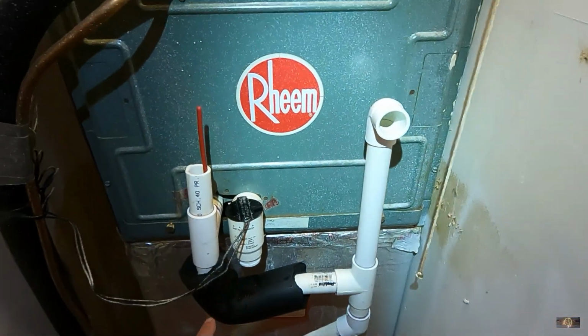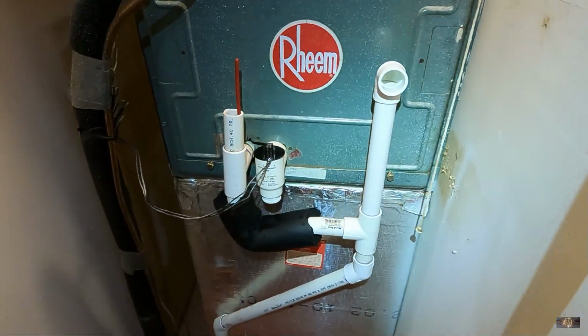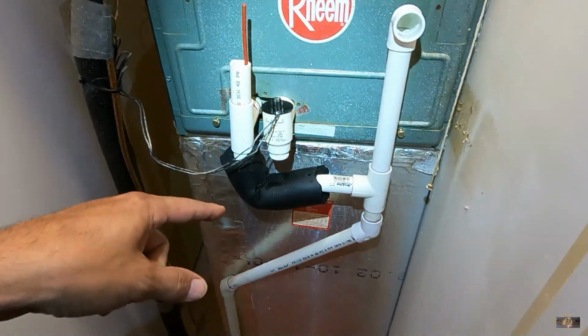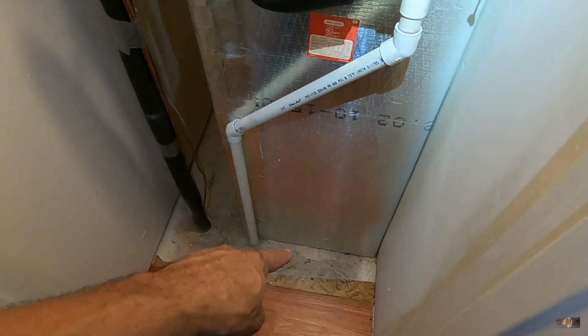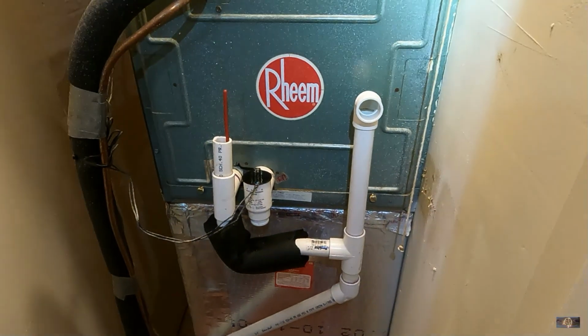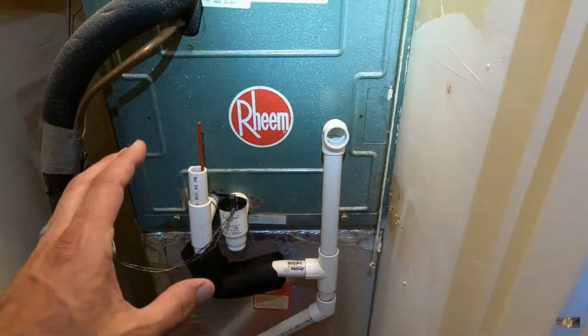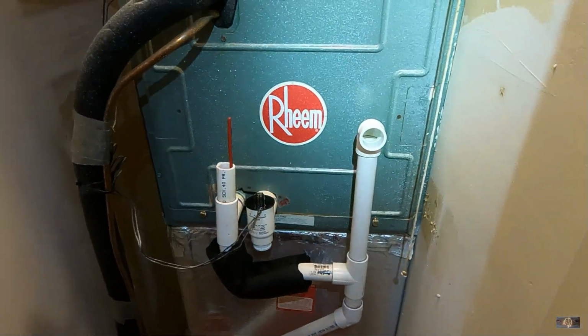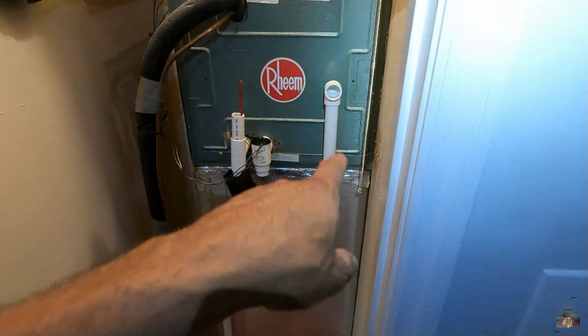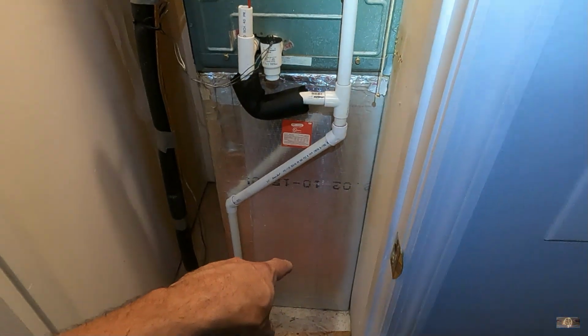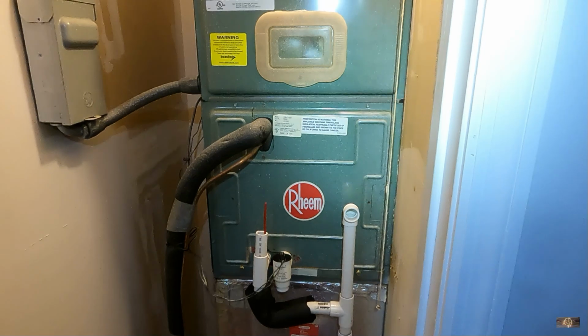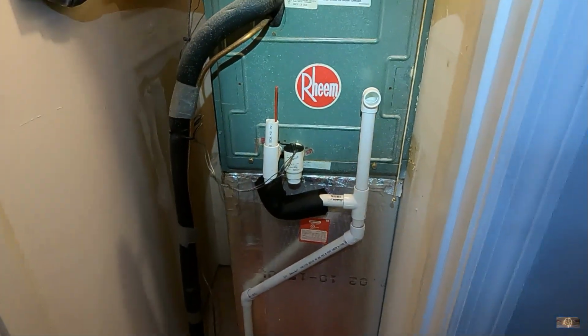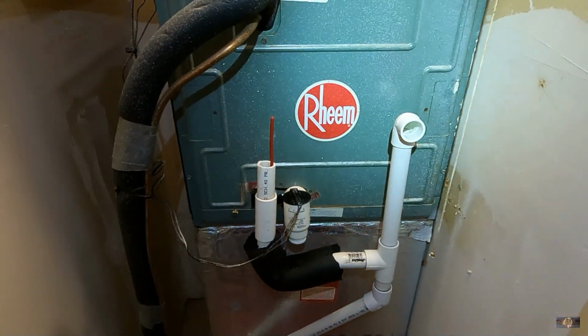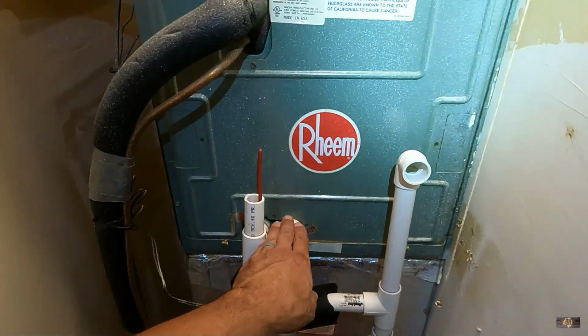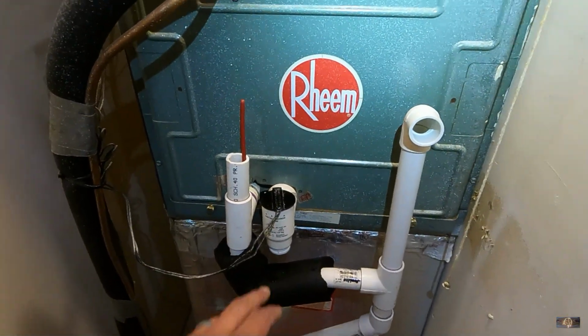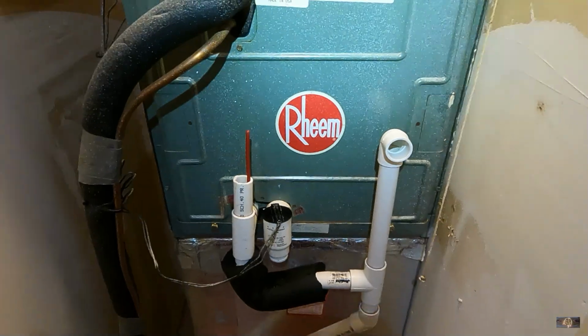I did suggest that we put a WS1 wet switch in this plenum, or right here, and break R to the thermostat so that if it detects any water, it'll shut the system down. I thought about dropping one down in that plenum, then running up and tying into the thermostat wires, putting it in series with this CS1. Because this is the only protection it has right now, so it's a little scary.